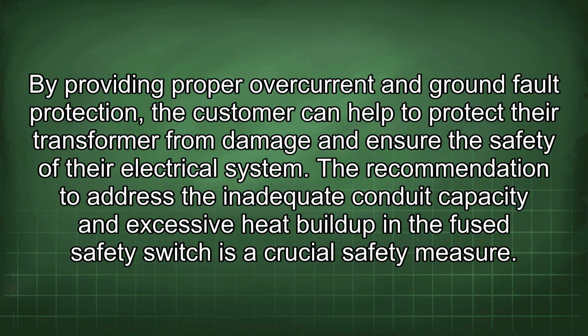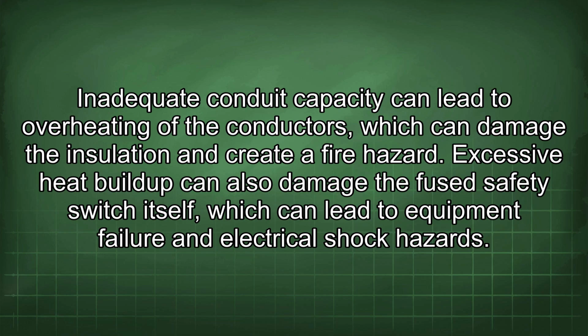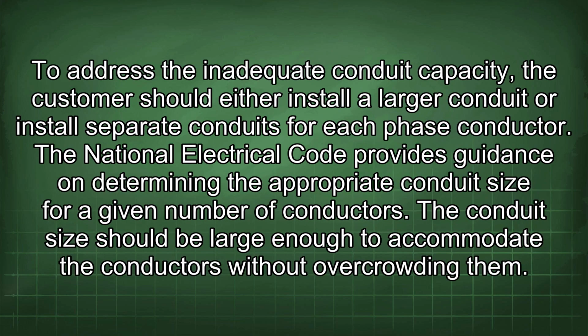The recommendation to address the inadequate conduit capacity and excessive heat buildup in the fused safety switch is a crucial safety measure. Inadequate conduit capacity can lead to overheating of the conductors, which can damage the insulation and create a fire hazard. Excessive heat buildup can also damage the fused safety switch itself, which can lead to equipment failure and electrical shock hazards. To address the inadequate conduit capacity, the customer should either install a larger conduit or install separate conduits for each phase conductor.